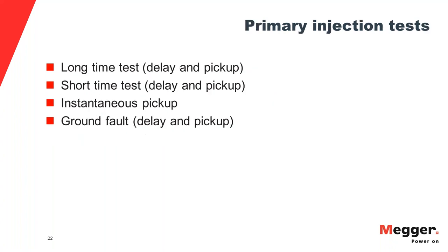There are four types of tests that are done as part of primary injection testing. There is long time test, there is short time test, there is instantaneous pickup, and there is ground fault. Let's talk about each of them. So you have the long time test.